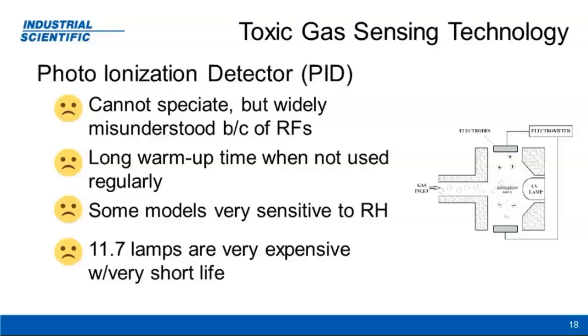There are multiple lamp voltages available, and some things you really need, like methanol, require that 11.7 EV lamp to detect. These lamps are very expensive and have a very short life. So if it's not something you're doing on a regular basis, and you need an 11.7 lamp to do it, you're probably better off going to some type of tube technology or other technology not typically used in a standard gas monitor, because you'll spend a fortune working through 11.7 lamps.